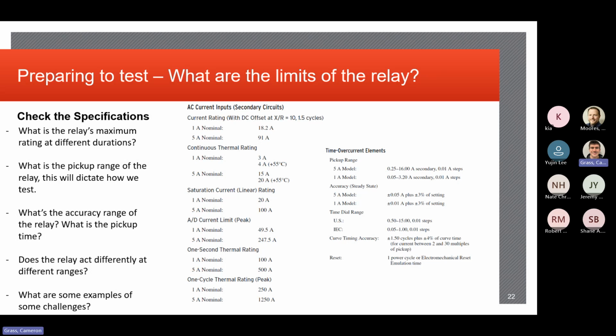That's a great question. That's fantastic. In the event that you are testing, for example, say there is a predetermined output, say OUT201, that's going to be tripping a breaker. That one we're going to be directly connecting to. The only reason we're connecting to a spare output is to measure specific elements that don't trigger a necessary output in that scenario, where you're trying to take a bit of information in the relay settings and monitor that element specifically, not a whole equation like a trip scenario where you have multiple different elements coming in and operating a specific contact. You're looking at just one little bit of information provided by the relay settings.